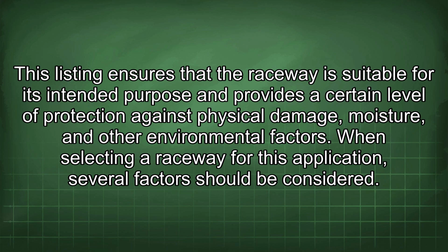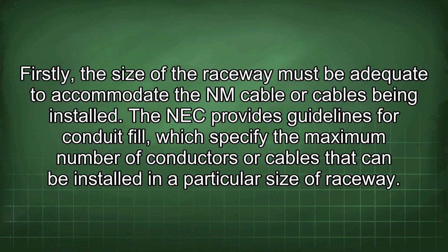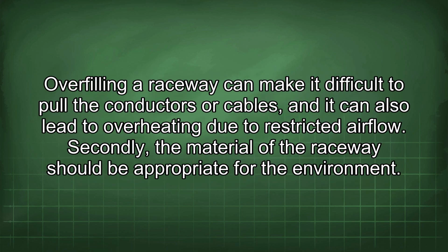When selecting a raceway for this application, several factors should be considered. Firstly, the size of the raceway must be adequate to accommodate the NM cable or cables being installed. The NEC provides guidelines for conduit fill, which specify the maximum number of conductors or cables that can be installed in a particular size of raceway. Overfilling a raceway can make it difficult to pull the conductors or cables, and it can also lead to overheating due to restricted airflow. Secondly, the material of the raceway should be appropriate for the environment.